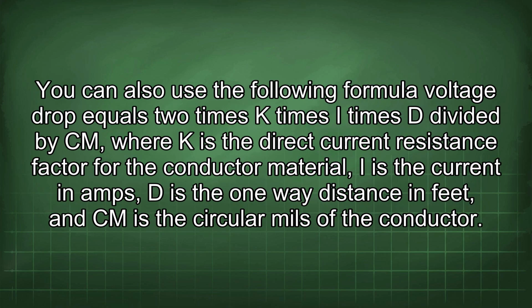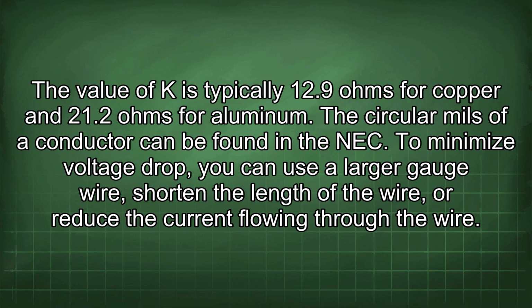You can also use the following formula: voltage drop equals 2 times K times I times D divided by Cm, where K is the direct current resistance factor for the conductor material, I is the current in amps, D is the one-way distance in feet, and Cm is the circular mils of the conductor. The value of K is typically 12.9 ohms for copper and 21.2 ohms for aluminum. The circular mils of a conductor can be found in the NEC.